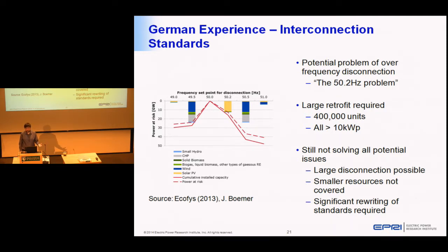That was fine then—there wasn't much solar, and it probably wasn't a time when there would have been solar production anyway, maybe early morning or late at night. But if you did have solar on there, a lot of it is actually required to disconnect at 50.2 hertz for anti-islanding safety reasons, so that if something weird is happening in the bulk power system and people go out to fix it, they don't find the solar still online—that's a big safety issue.